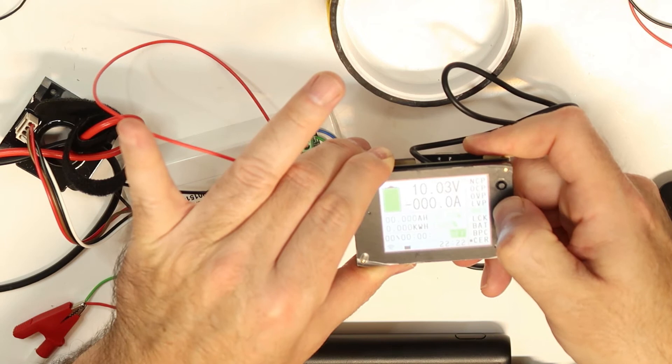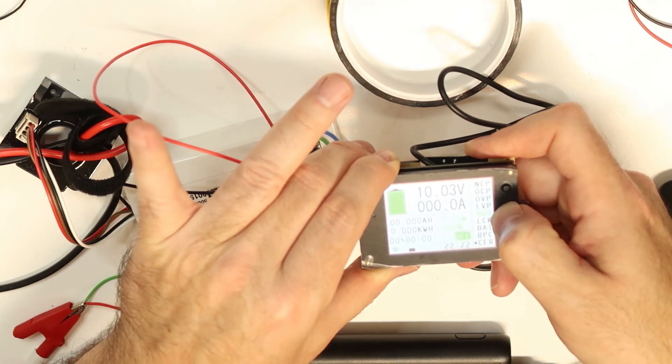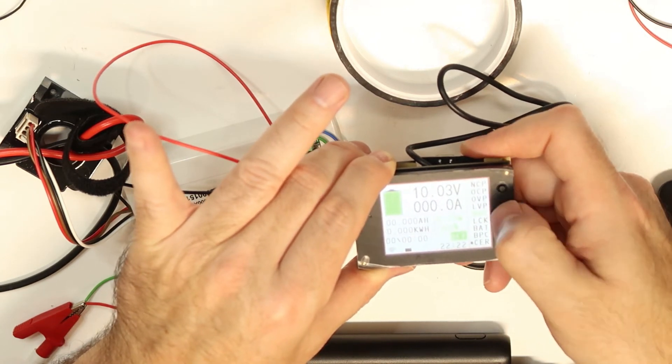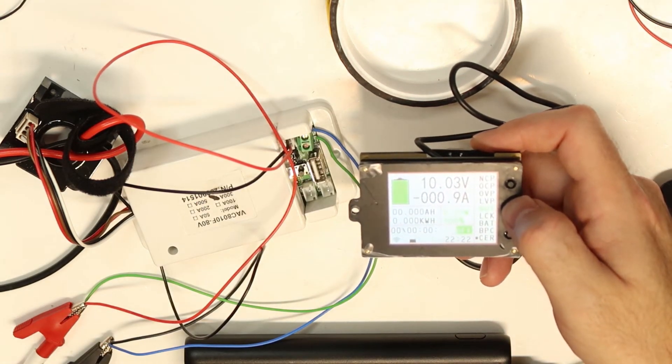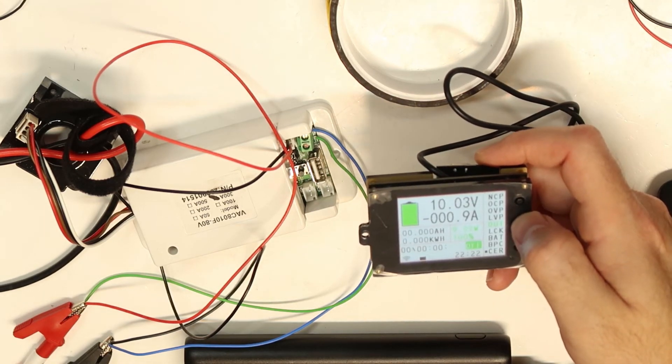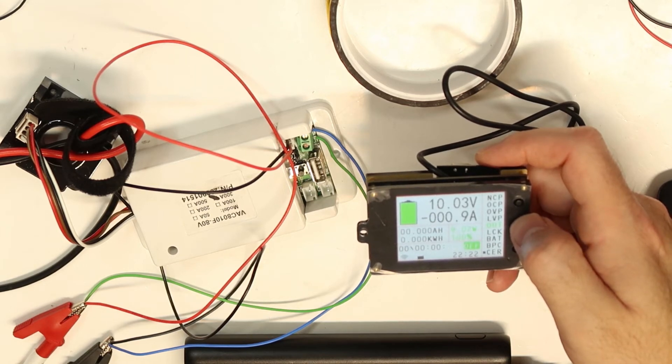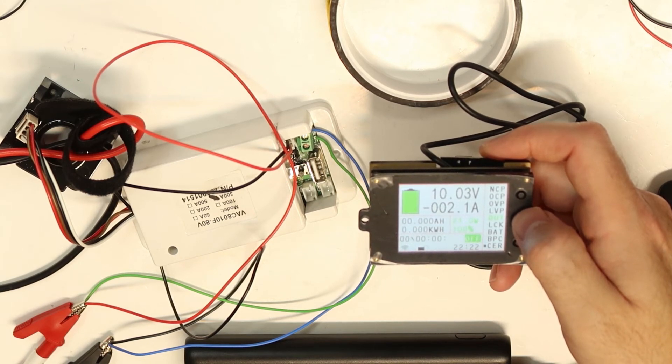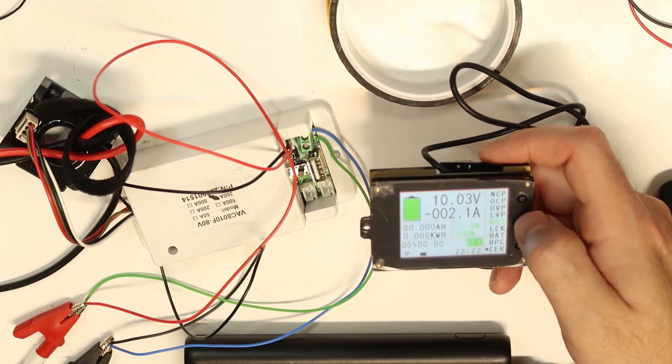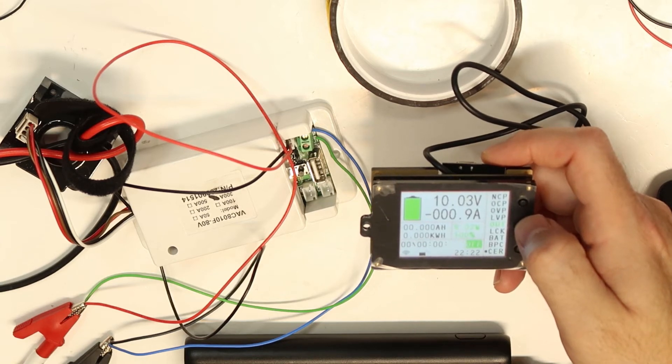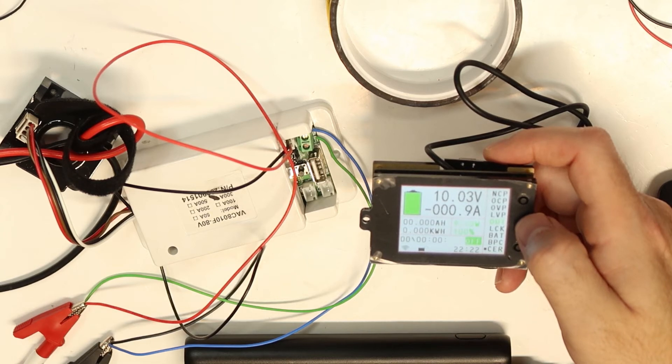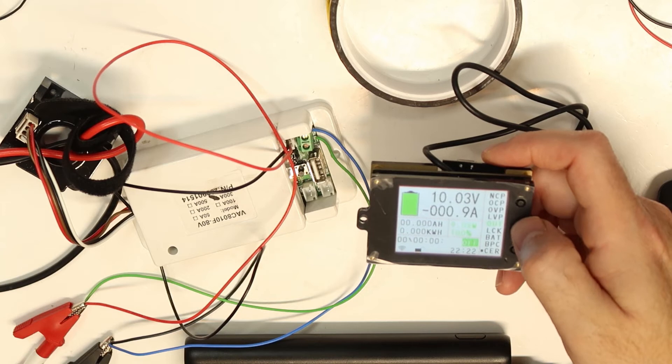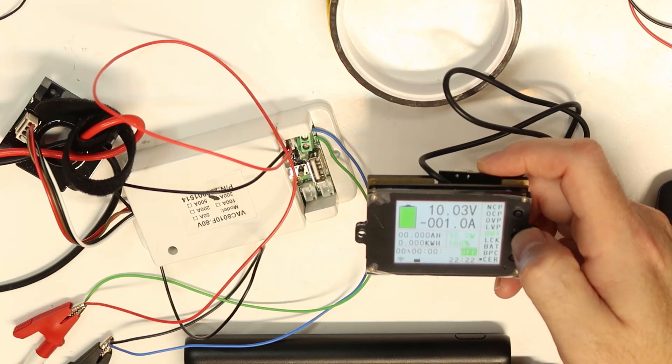This should do the reset. Let's see. Yeah, it is now better but it is yet a little incorrect. I will put two amps and we'll see. Ah, 2.1, okay so it's pretty, pretty, pretty okay. I put again one amp - 1.1 amp, give me probably one amp. Okay, it's pretty acceptable. There is an error of 100 milliamps and I'm talking about a 300 amp model, so this is probably acceptable.